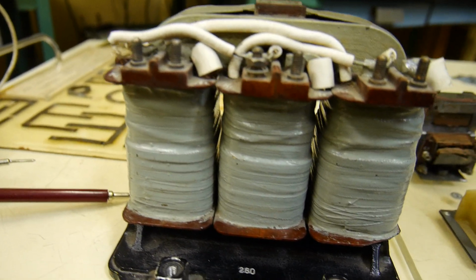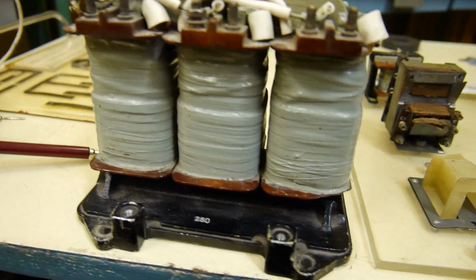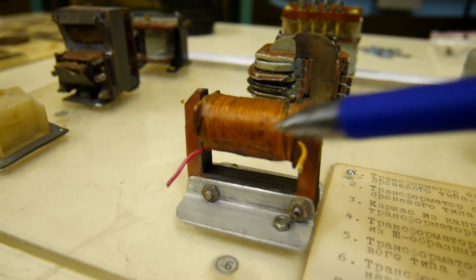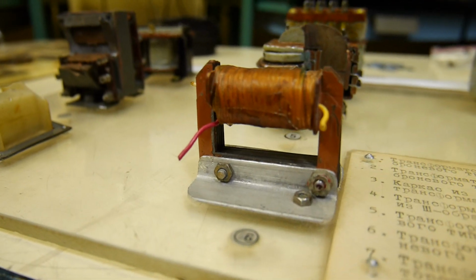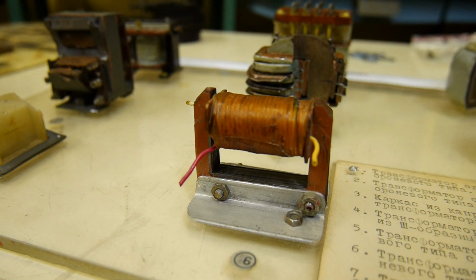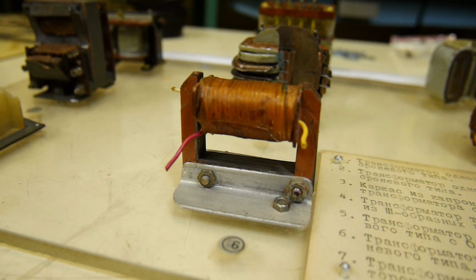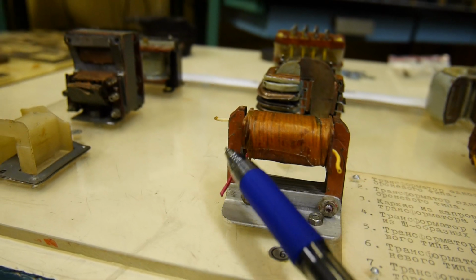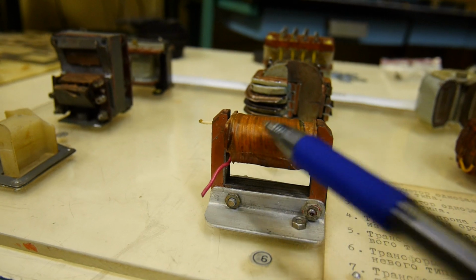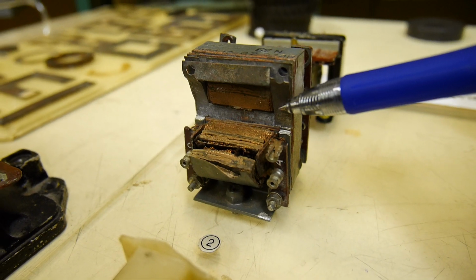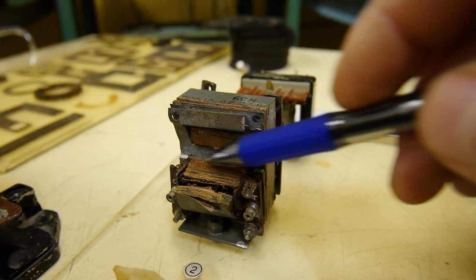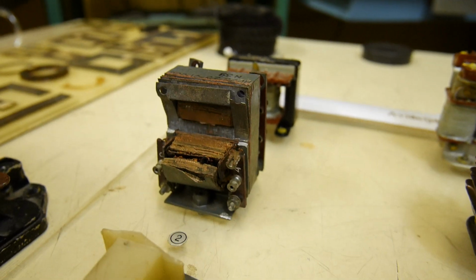The transformer can be three-phase, like this, or it can be single-phase. For example, this small guy is a single-phase transformer. The single-phase transformers can be of three types. The first of them is a core type, where the core goes outside of the transformer and the windings are here. The second one is a shell type, when windings are inside, like in a shell, and the shell is made of the magnetic conductor. And the third type is toroidal.